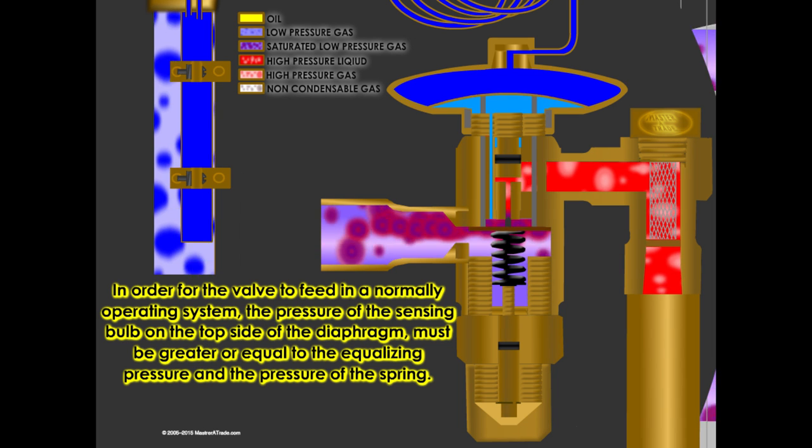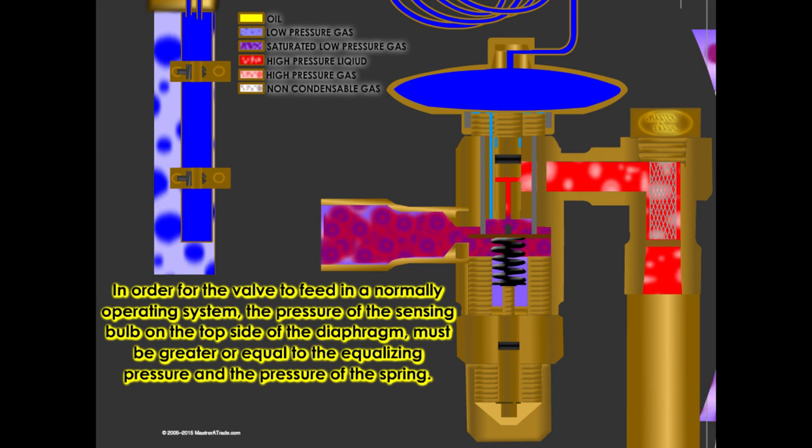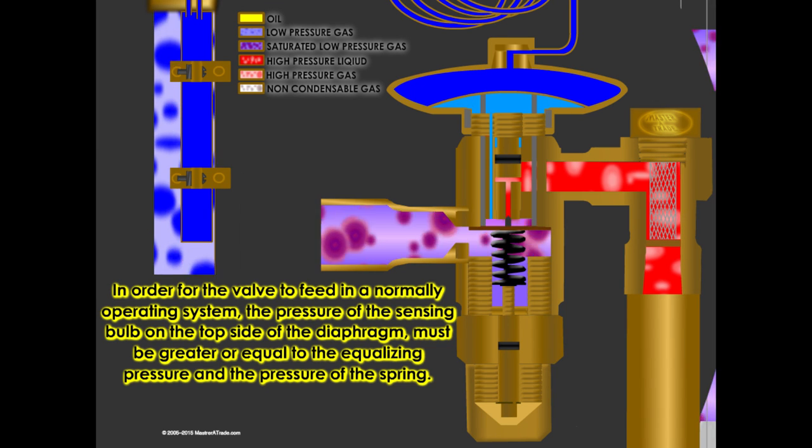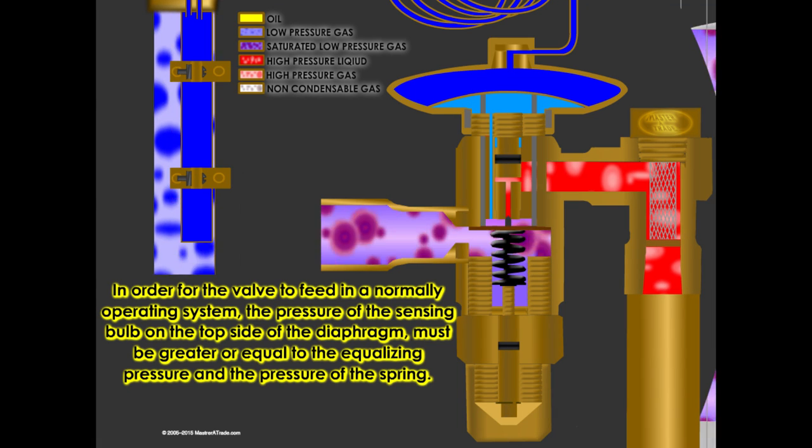In order for the valve to feed in a normally operating system, the pressure of the sensing bulb on the top side of the diaphragm must be greater or equal to the equalizing pressure and the pressure of the spring.